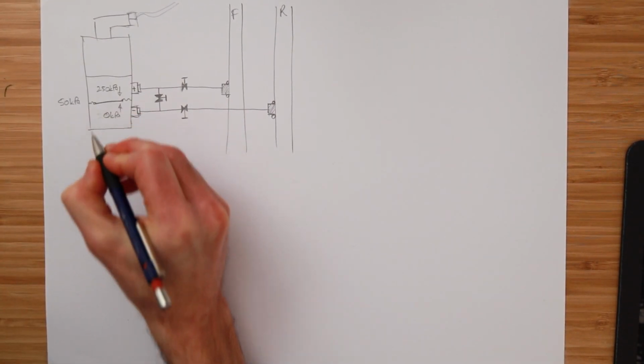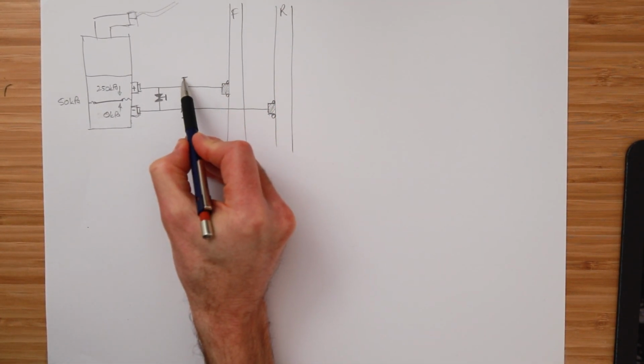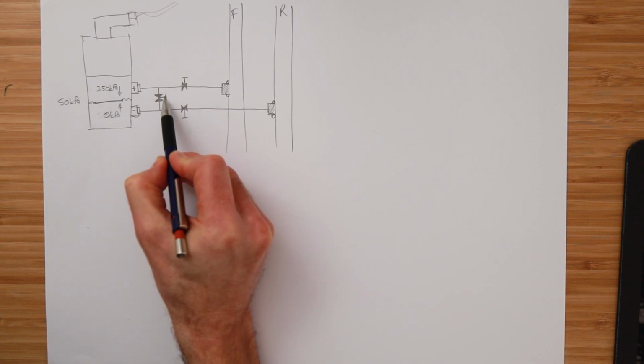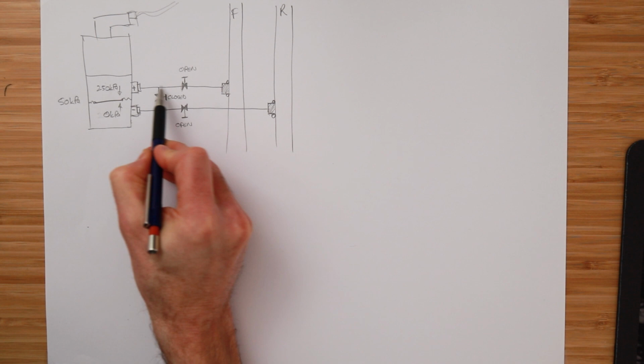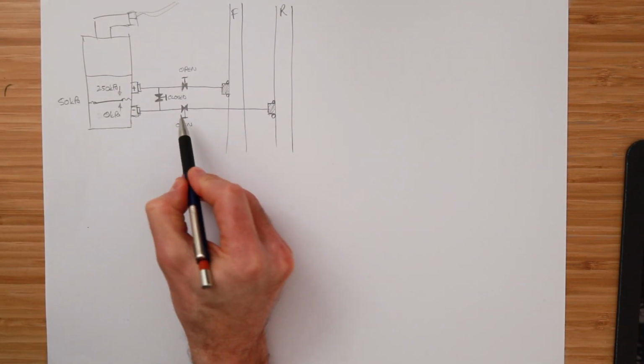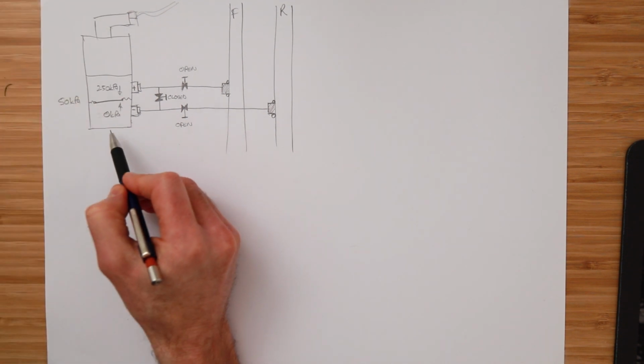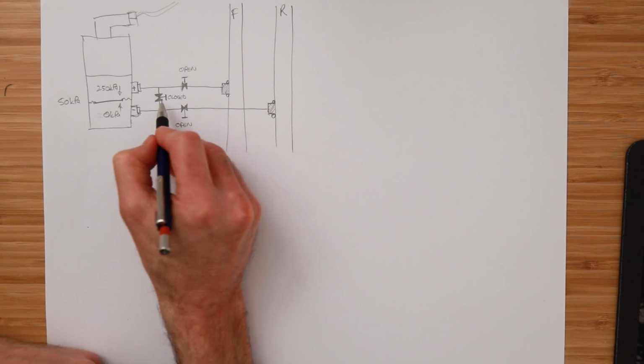and let's say this was closed, so we've got the static head of the building through this open mini isolation valve. If this is closed, if that 250 comes through here and sits on here and presses on the diaphragm, and this is closed, there's nothing here, it'll burst the diaphragm, the sensor will fail and need to be replaced. So that's why we have this bypass valve in the middle here.